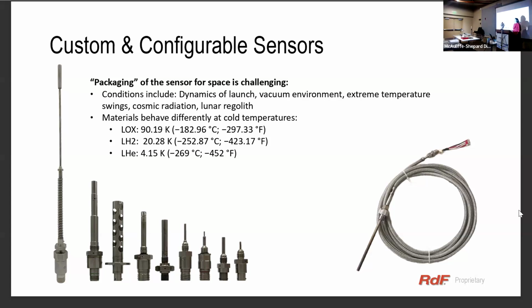Pretty simple, pretty straightforward. But over here you have a picture of a probe used in the space shuttle fuel lines. It has a hollow area at the top, and the sensor is wound around that hollow area. This optimized the sensor for an extremely fast response time in liquid hydrogen, about 20 degrees Kelvin, where everything moves slow and readings are slow, and materials act funny at liquid hydrogen temperatures, which is why the sensor needed this design.